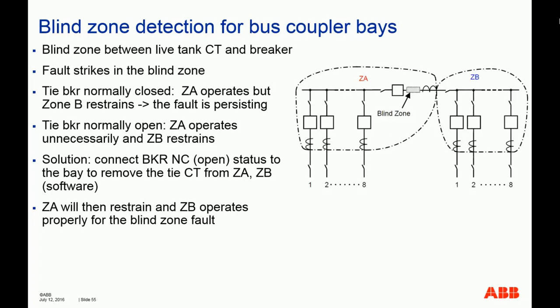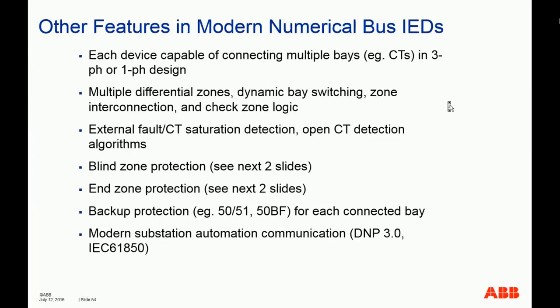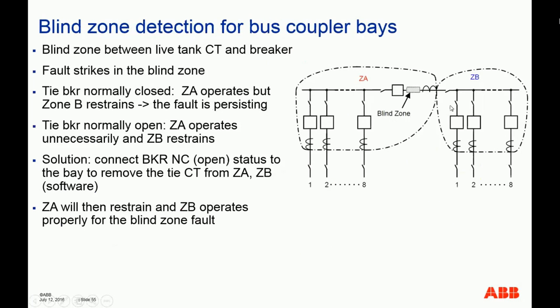Okay, blind zone detections. We talked about this a little bit. So basically, we have only a single CT, not overlapping with each other. If the tiebreaker is operated normally closed, zone A will operate because of the CTs, if the fault strikes here, but zone B will restrain, because that's outside the zone. If the tiebreaker is normally open, again, zone A will operate, but the fault is still there, it's not cleared, but zone B will restrain.